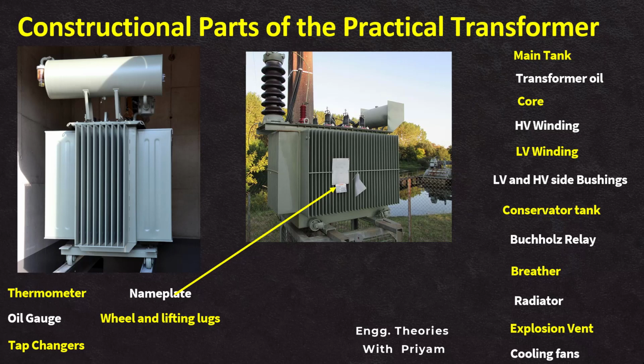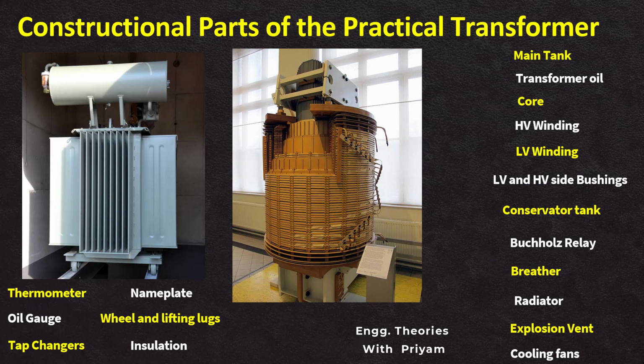Next, we want to talk about the insulation inside the transformer. The insulation in the majority of transformers consists of both oil and cellulose or paperboard. The solid insulation is divided into major and minor insulation structures. The major insulation structure system includes barriers, spacers, and clamps, while the minor insulation consists of winding insulation.